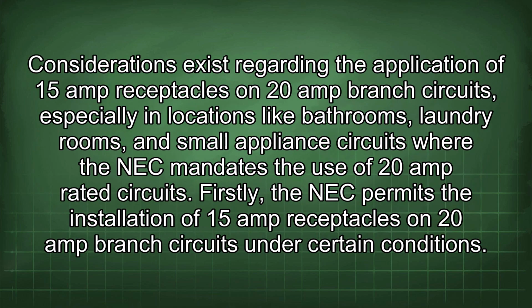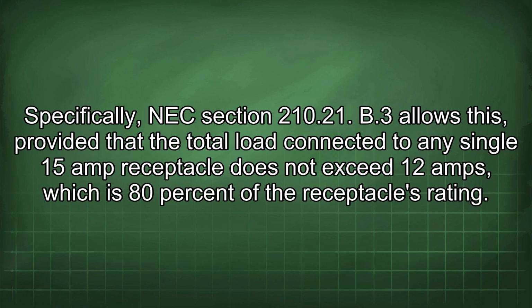Considerations exist regarding the application of 15-amp receptacles on 20-amp branch circuits, especially in locations like bathrooms, laundry rooms, and small appliance circuits where the NEC mandates the use of 20-amp rated circuits. Firstly, the NEC permits the installation of 15-amp receptacles on 20-amp branch circuits under certain conditions. Specifically, NEC Section 210.21(B)(3) allows this, provided that the total load connected to any single 15-amp receptacle does not exceed 12 amps, which is 80% of the receptacle's rating.